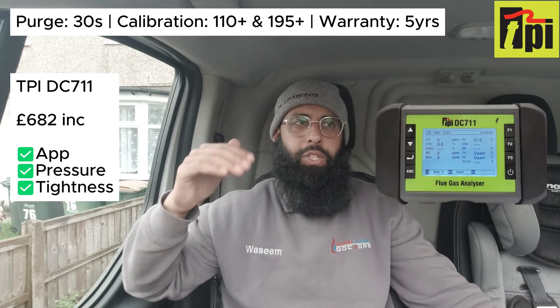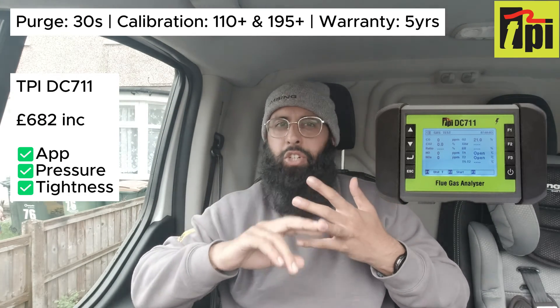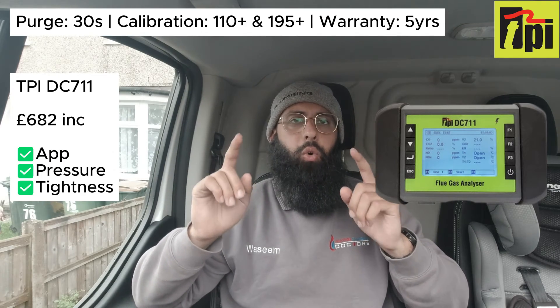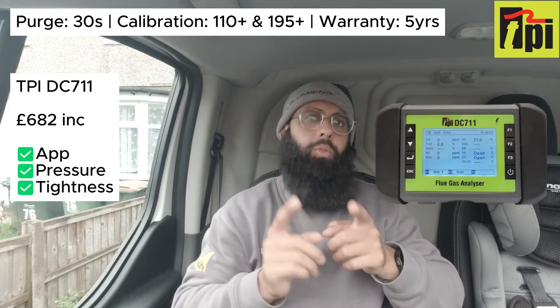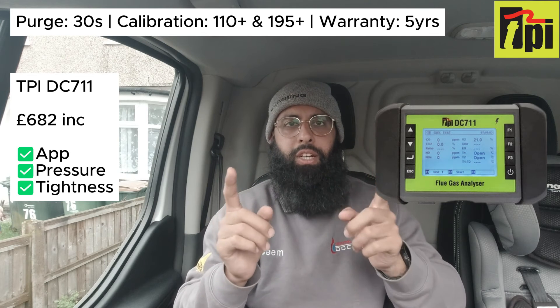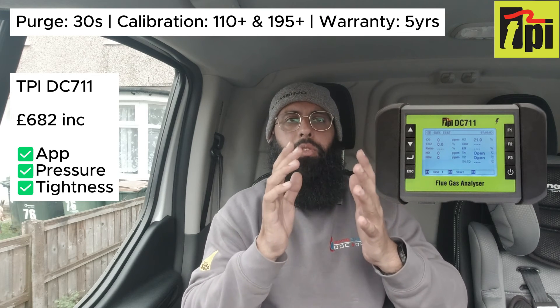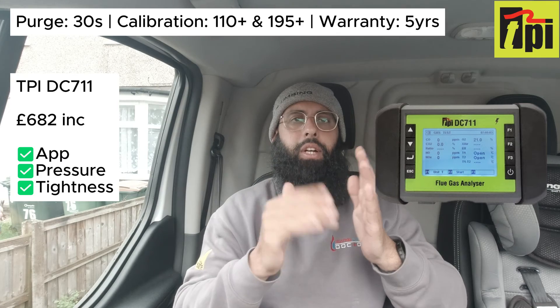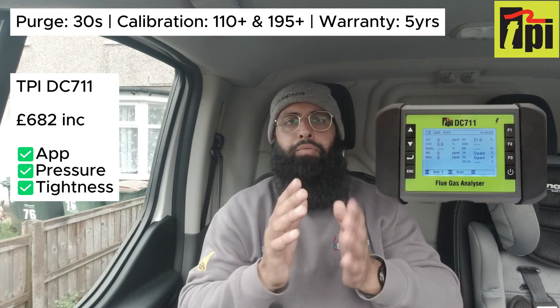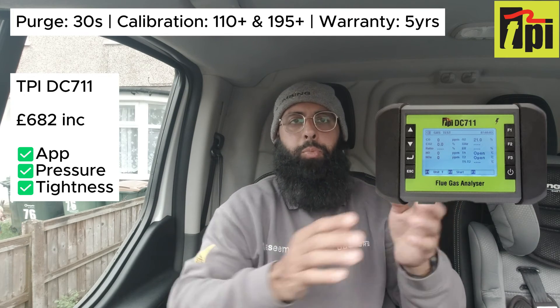The TPI 711 doesn't do leak detection and it doesn't have a touchscreen colour display, but you can connect all TPI instruments to the app — similar to Kane. It gives live view of pressures and temperature differentials on the app rather than the FGA screen itself. You can create a report and send it to yourself. I believe you can also do geo-tagging, so if you want proof that you were at a specific location servicing a specific boiler, you can include your location on the report.